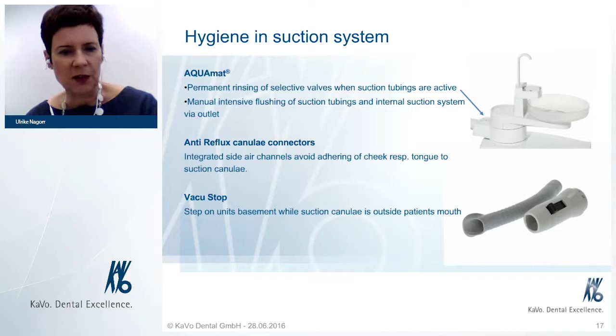The third feature that also is available here is the vacuum stop in all KaVo treatment units. When the user, either the dentist or the assistant, is stepping on the basement top of the treatment unit, the complete suction is switched off. That means there is no need, when you don't like to have the suction, to close the suction cannula itself with the fingers, which is not so hygienically recommended.